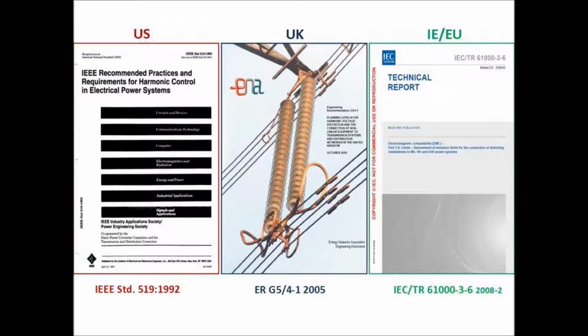I suppose just to talk about each of them, they all try to do the same thing, and that is impose a limit at the point of common coupling, where whatever user connects onto the grid. The US one tries to do it in a very harmonised way, in that it supplies current and voltage distortion limits that are agreed between the user and the system operator. The UK one puts the onus on the user and basically says that it's first come, first served.